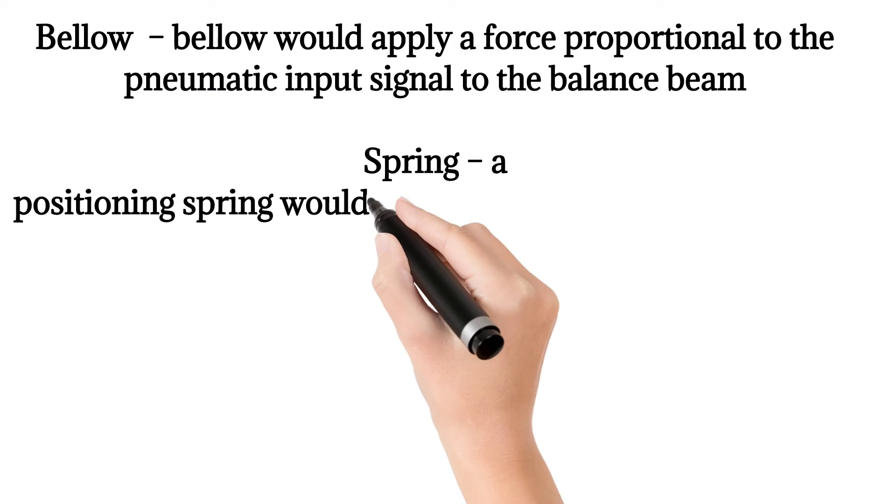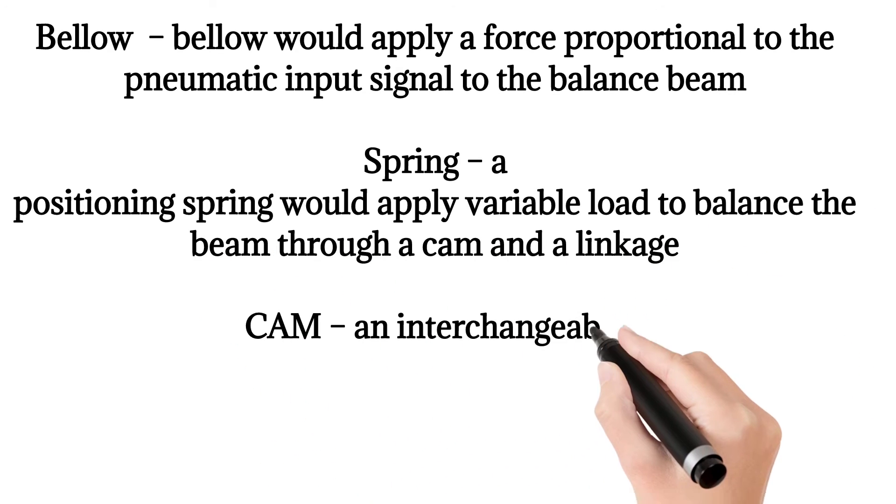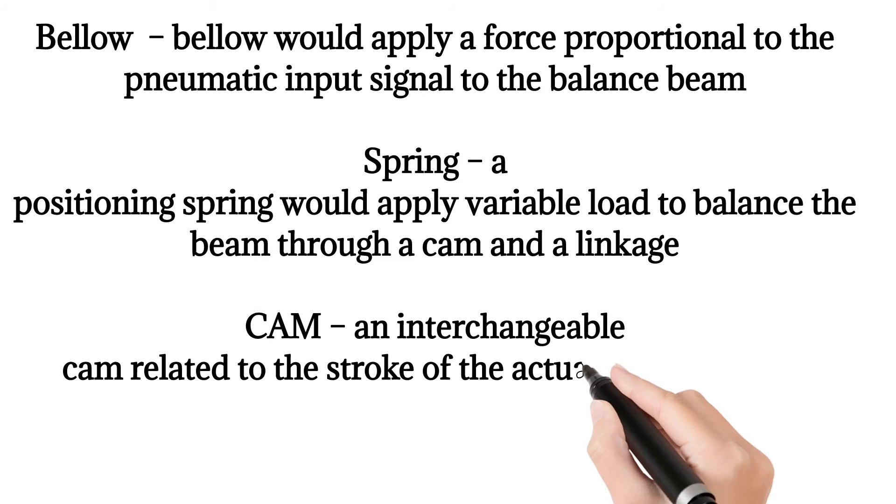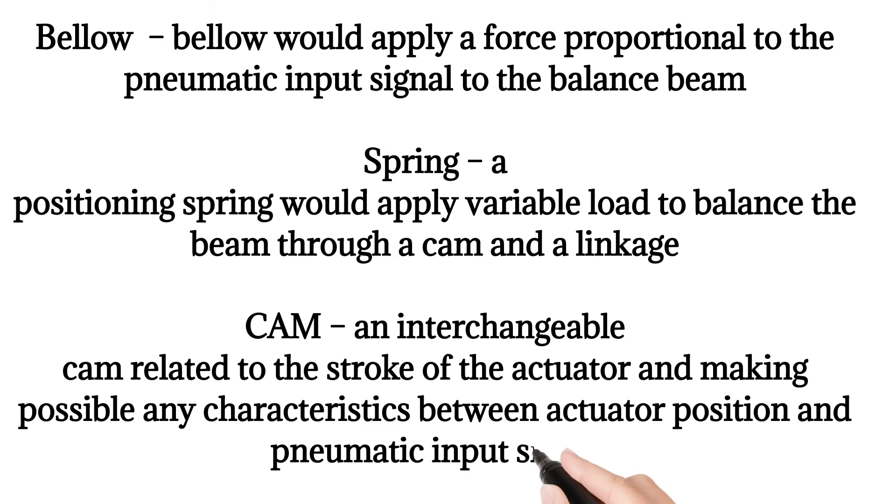A positioning spring would apply variable load to balance the beam through a cam and a linkage cam, an interchangeable cam related to the stroke of the actuator and making possible any characteristics between actuator position and pneumatic input signal.